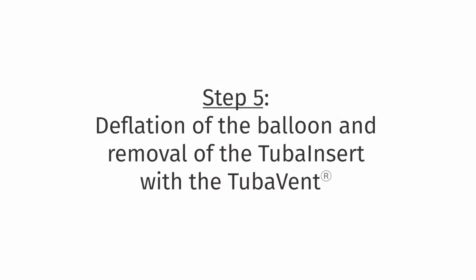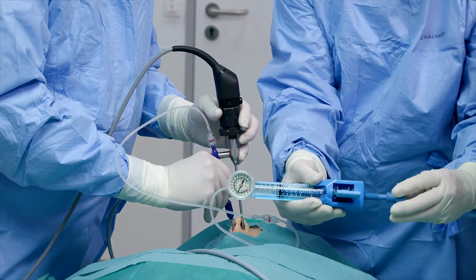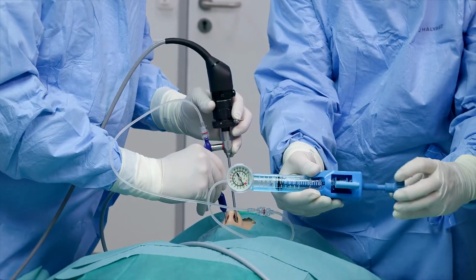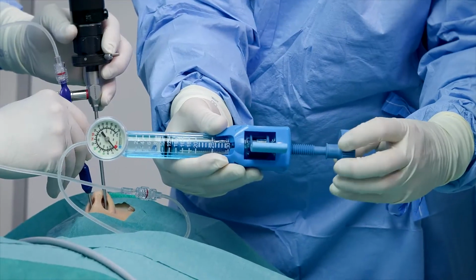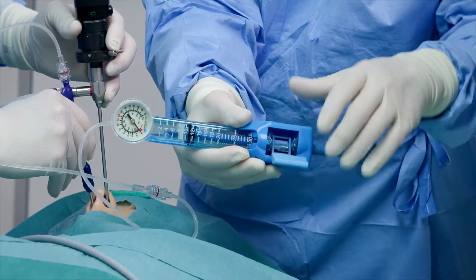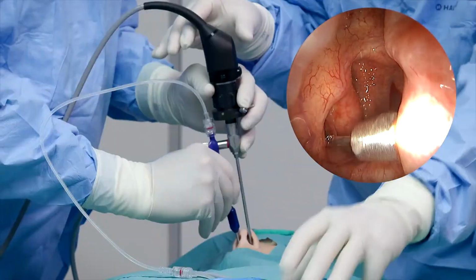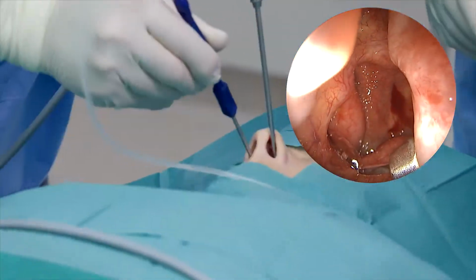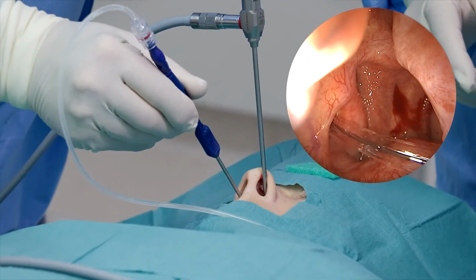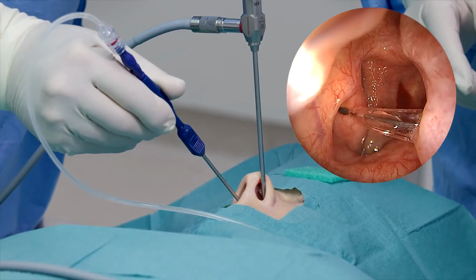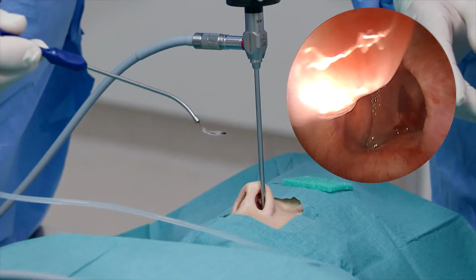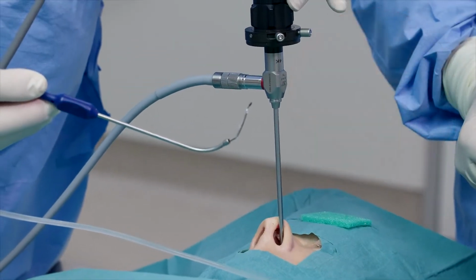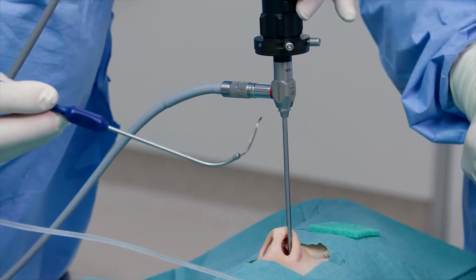Step 5. Deflation of the balloon and removal of the TubaInsert with the TubaVent. After 2 minutes, reduce the pressure completely by turning the plunger of the inflation device counterclockwise and lock the device by switching the lever into the center position. The removal of the catheter should be done under endoscopic supervision. The catheter and insertion device should be withdrawn together, ensuring that the balloon remains outside of the insertion device. In addition to the contralateral access, the eustachian tube can also be accessed via the ipsilateral or pharyngeal path.